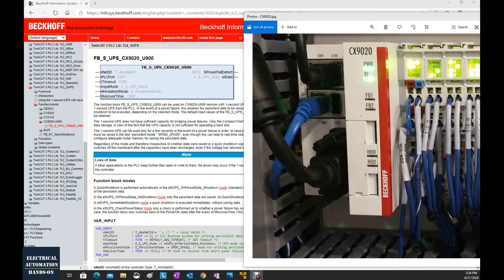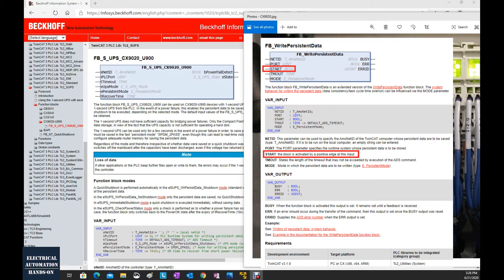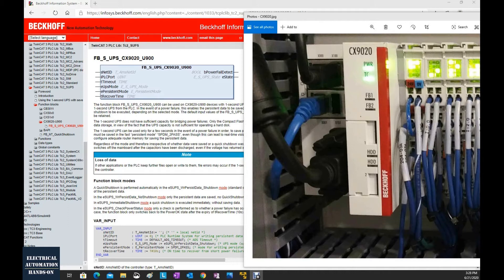As we introduced in one of the previous videos, there is a write persistent function block. The function block allows the controller to retain variables that have persistent properties. However, to retain the variables, we need to trigger that write persistent function block. Sometimes if your system shuts down the power by accident or for some unknown reason, you will still lose data, especially for some important parameters — for example, PID parameters or some recipe values inside the controller.